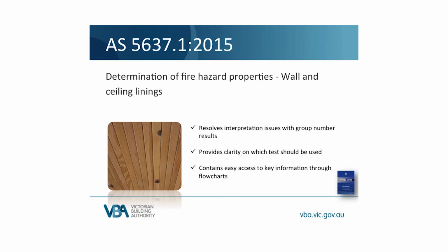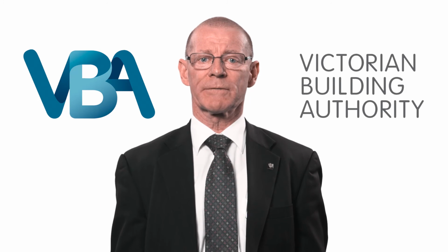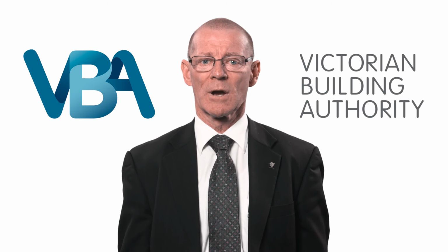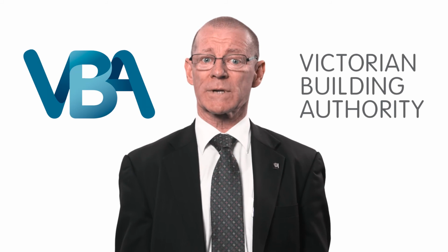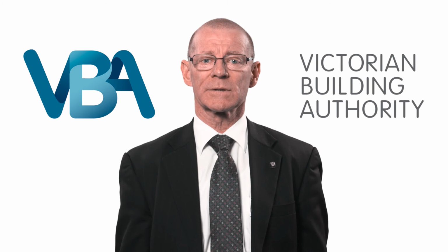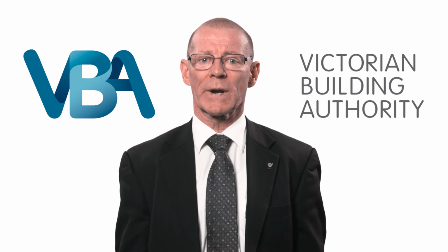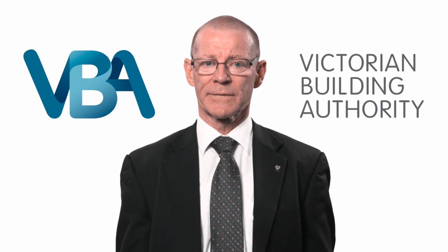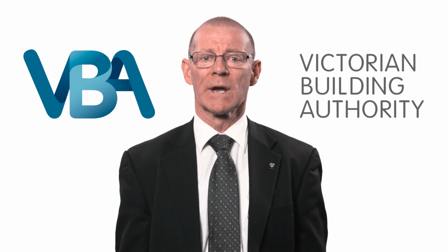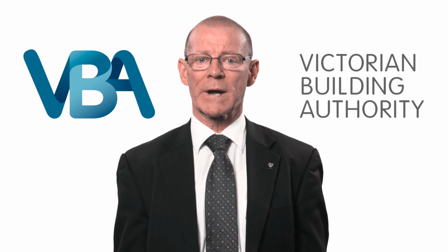The standard, amongst other things, clarifies the types of lining systems where small-scale tests, AS/NZ 3837, may not be appropriate, and large-scale tests, as per AS/ISO 9705, should be performed. The NCC allows 2 different methods for determining group numbers, one for large-scale and one for small-scale. There were discrepancies between the results for some products depending on the method used. This standard was developed to address this issue and ensure that building materials are properly rated.